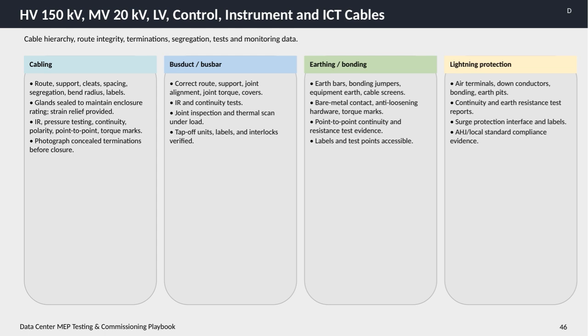Testing includes insulation resistance, pressure testing for ducts, continuity checks, polarity verification, point-to-point confirmation, and torque mark inspections. Additionally, photographing concealed terminations prior to closure helps document the quality of the installation. Moving to bus duct and bus bar systems, the focus is on ensuring the correct routing and support so that joints are properly aligned and tightened with the specified torque. Covers must be securely in place. Insulation resistance and continuity tests are performed thoroughly. Joint inspection under load, including thermal scanning, is done to detect any issues. Tap-off units are checked along with labels and interlocks to guarantee operational safety and reliability.